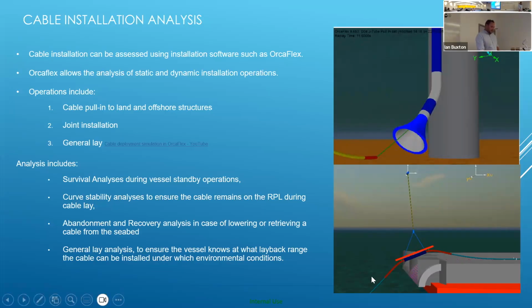You can see here they're overboarded with what's usually a spreader frame with a complex rigging situation to try and avoid any additional forces going through that joint. Bearing in mind 7 to 10 days jointing activity, you do not want to have to repeat that. So it's very important that you run the Orcaflex analysis to understand your installation parameters to allow you to install that safely and avoid you having to repeat a 10-day jointing time.